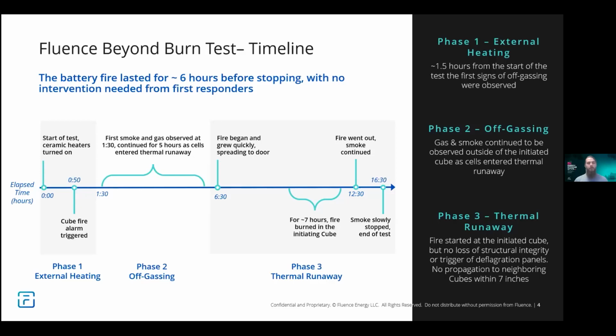It's important to note that throughout this test, all the adjacent cubes had live modules in them. We were trying to figure out if, by pushing our equipment to extreme circumstances, the fire would propagate to the next cube over. Additionally, there was zero water put on this test, and ultimately the smoke at the end of the day just stopped. It was really good.